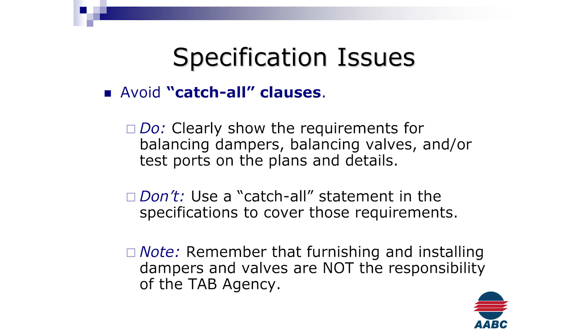So do clearly show the requirements for balancing valves, dampers, and/or test ports on the plans and details. A detail is a balancer's best friend. Because if I have a really good detail about a branch takeoff, for instance, that shows a quadrant damper with a standoff and a locking nut on it, when I get to that damper I know exactly what to expect. If there's no detail on the job and I start getting into 6-inch rounds and find 1/4-inch volume dampers, that's a problem.